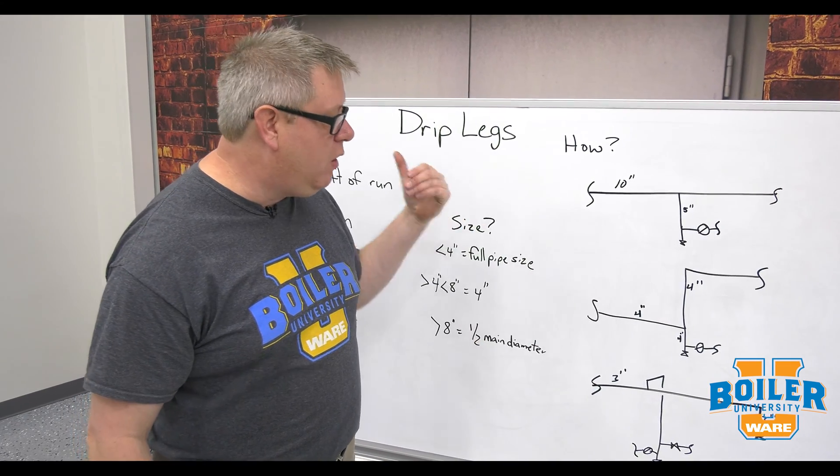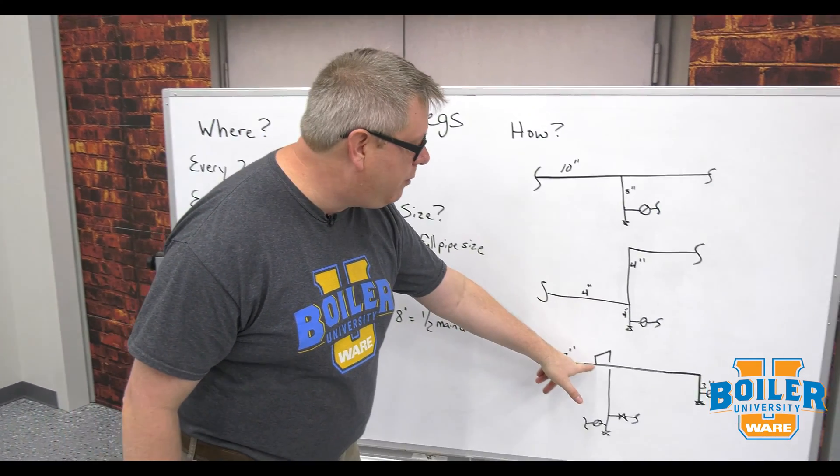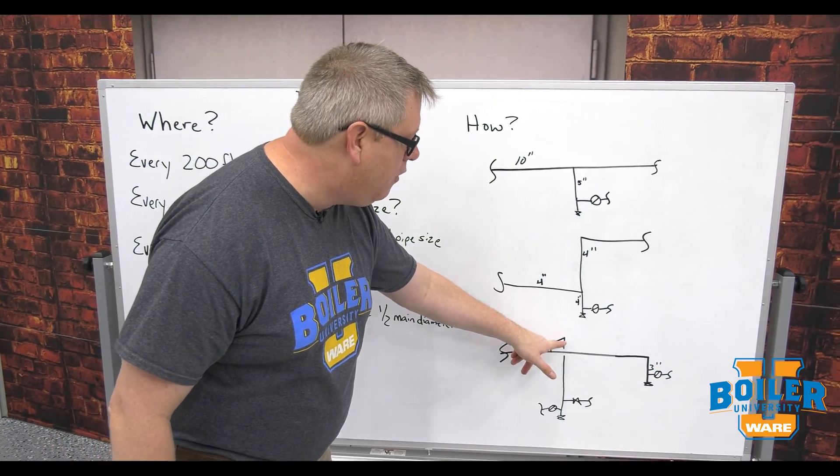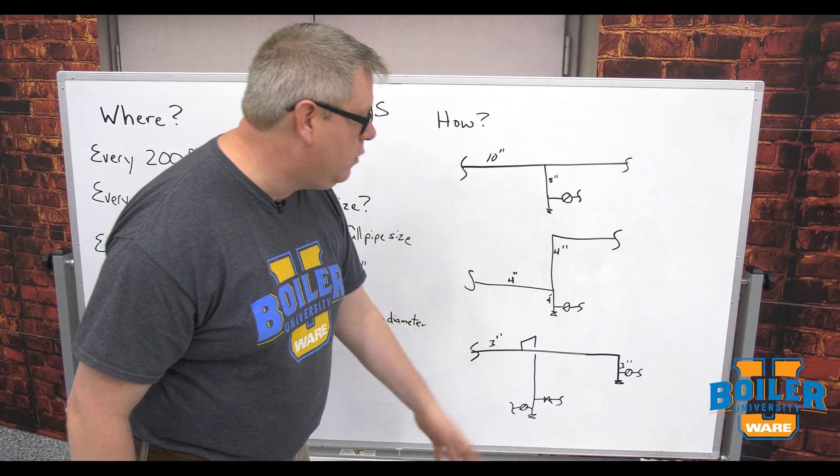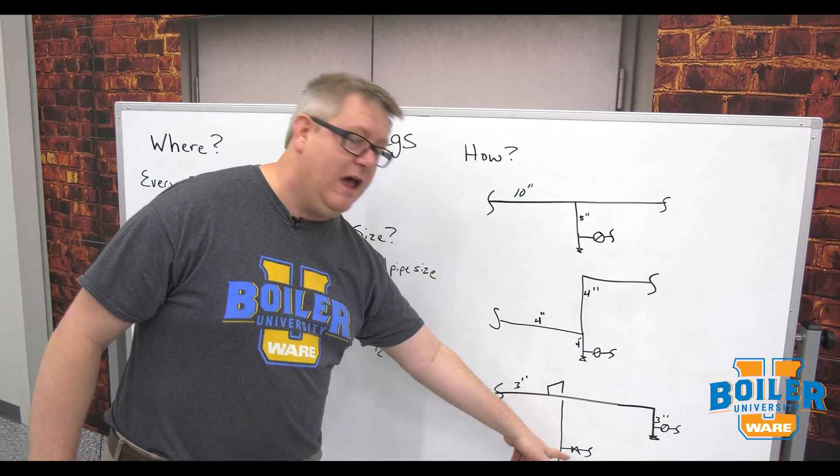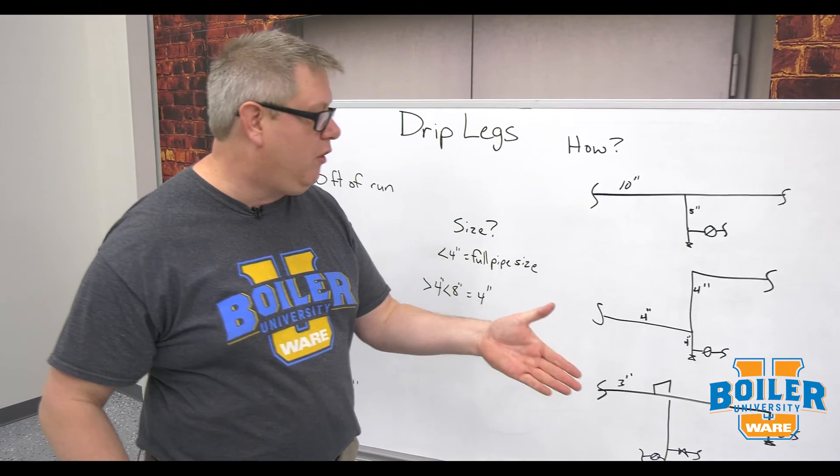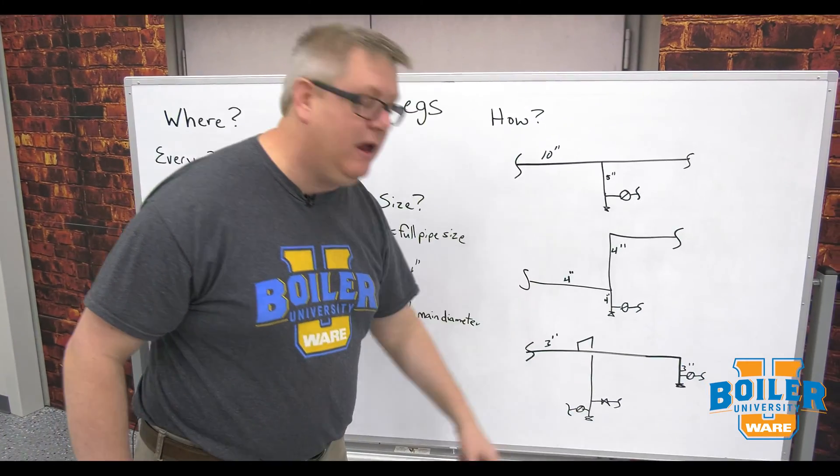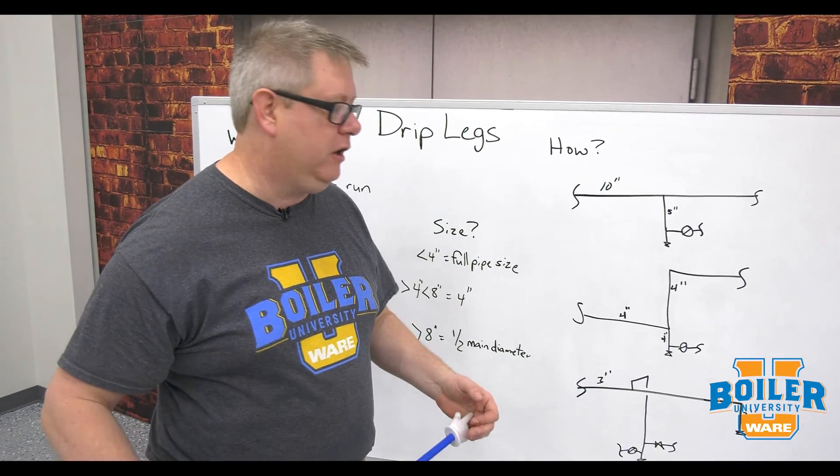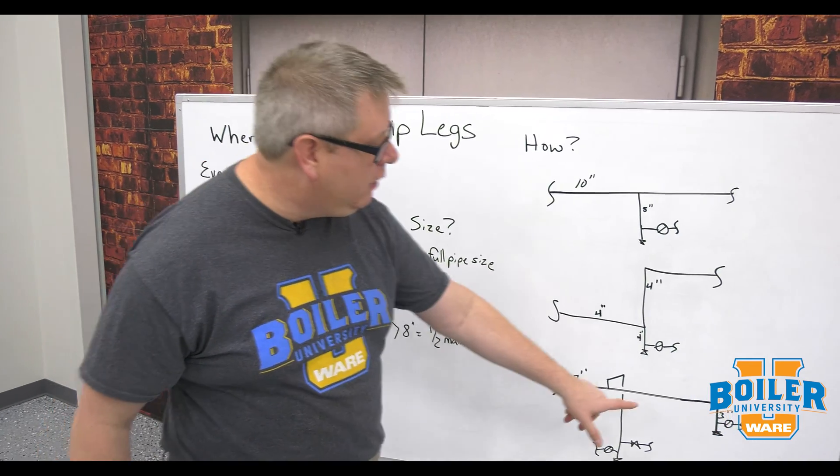So we want to pull off the top of the pipe, over a 90, down to our equipment. And because that equipment's going to have some sort of isolation or control valve, we're going to have a trap down there to keep that header clear.